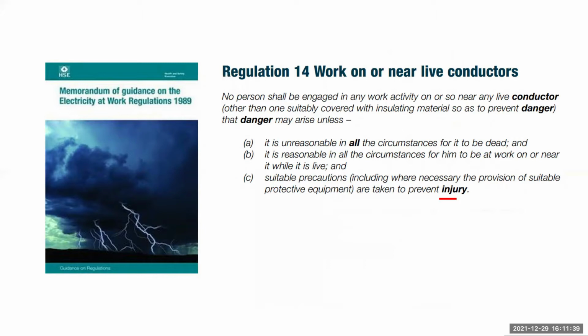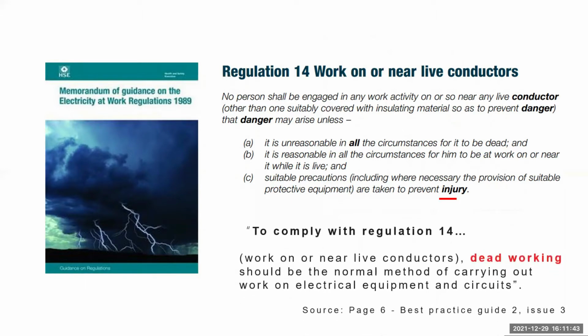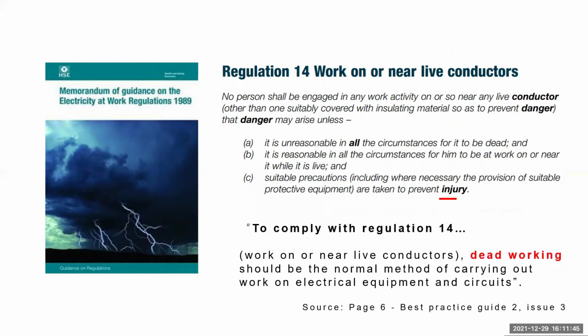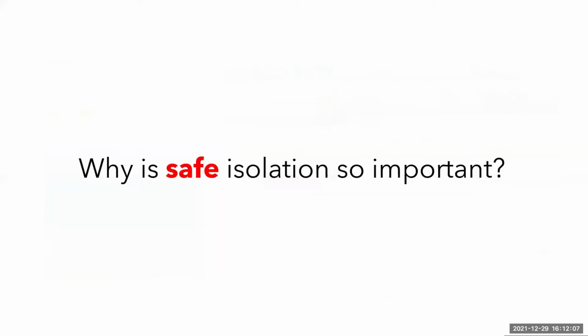To comply with Regulation 14, work on or near live conductors, dead working should be the normal method of carrying out work on electrical equipment and circuits. We can comply with this regulation by safely isolating the live conductors at various points within the installation before we gain access to them. In the majority of situations, there should not be many reasonable circumstances where the installation should be live, but every job should be taken on its own merits.